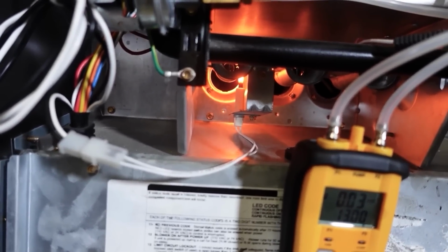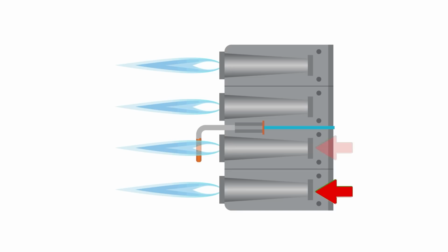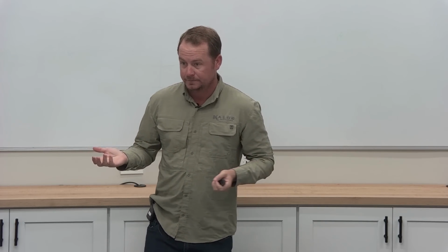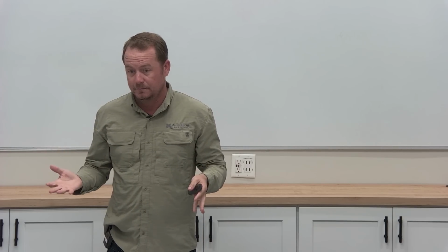We need to make sure the gas valve is on, we need to make sure the gas supply is on, we need to make sure that we don't have leaks, but then we need to run that furnace and look at the flames and make sure that everything is aligned properly. In a lot of cases, you get a burner that's kind of off and now all of a sudden that flame is impinging, which means the flame is hitting metal. If that flame hits metal long enough, stuff is either going to melt or get damaged. It's a problem, and then you're going to have safety issues.